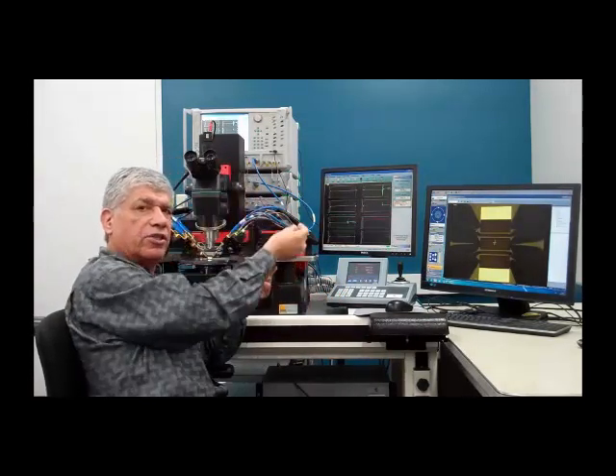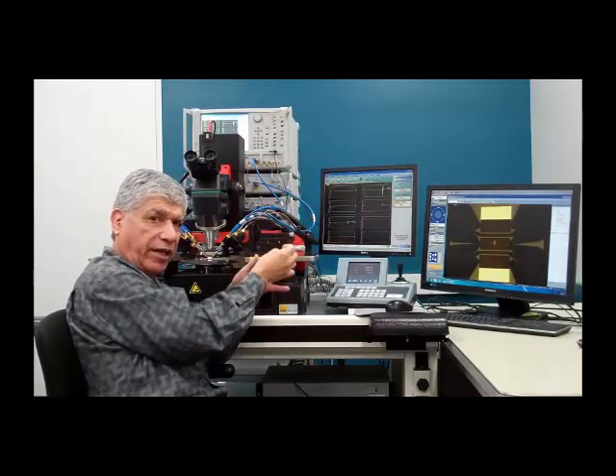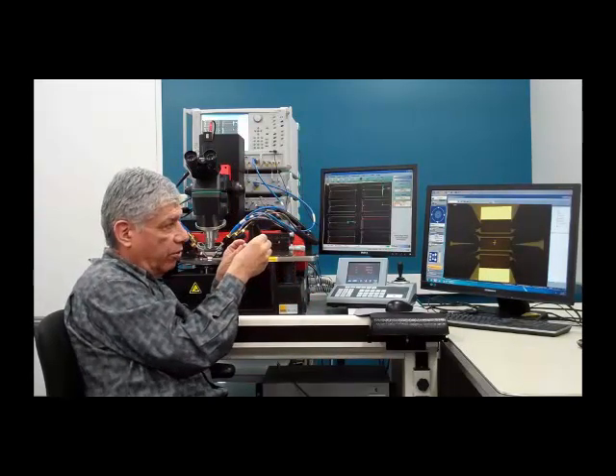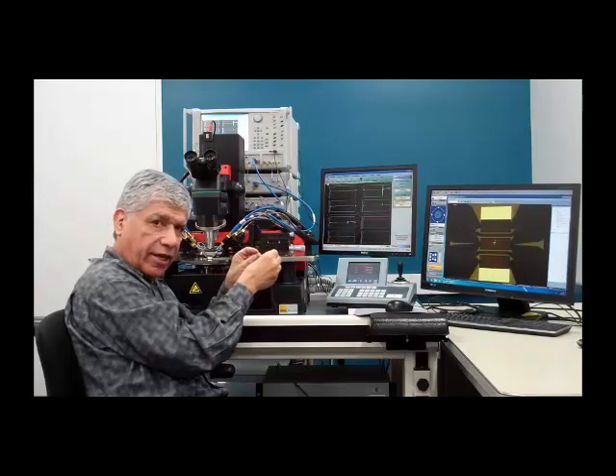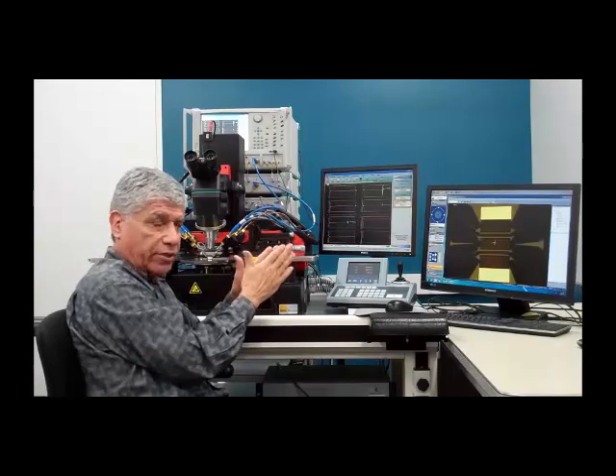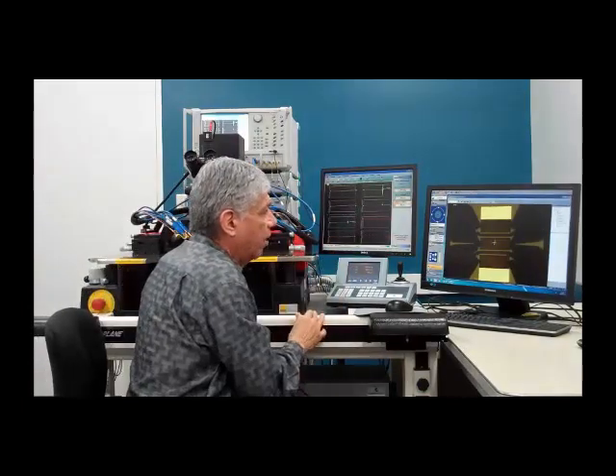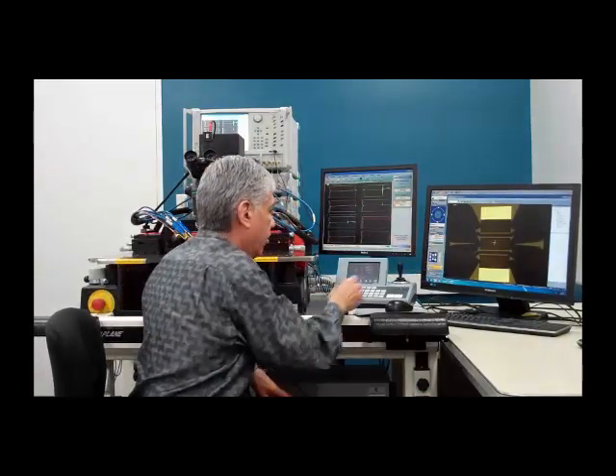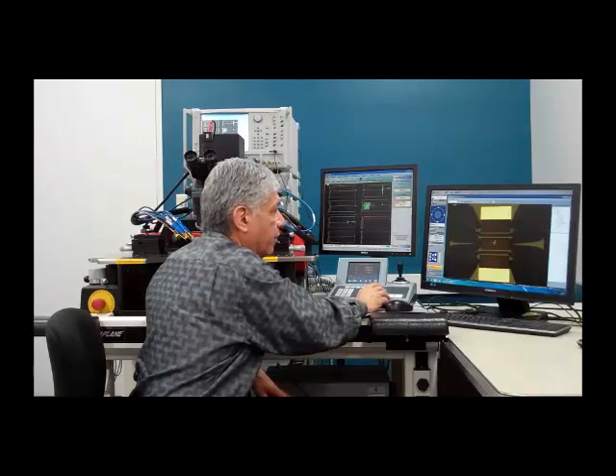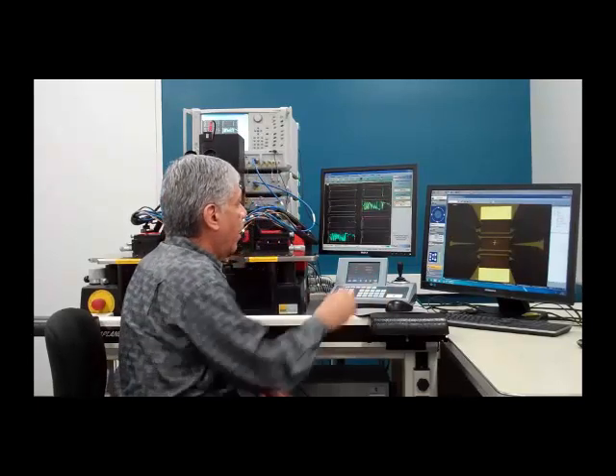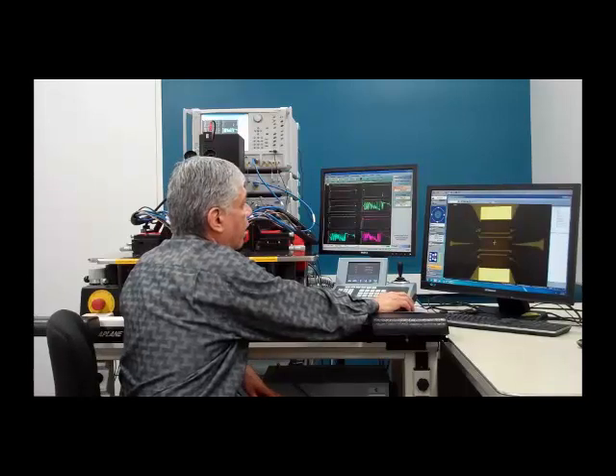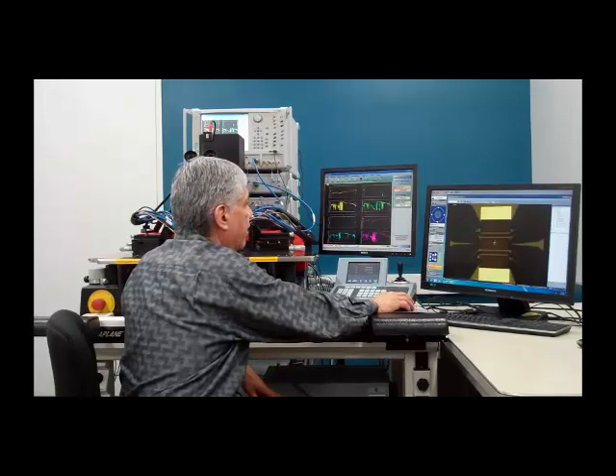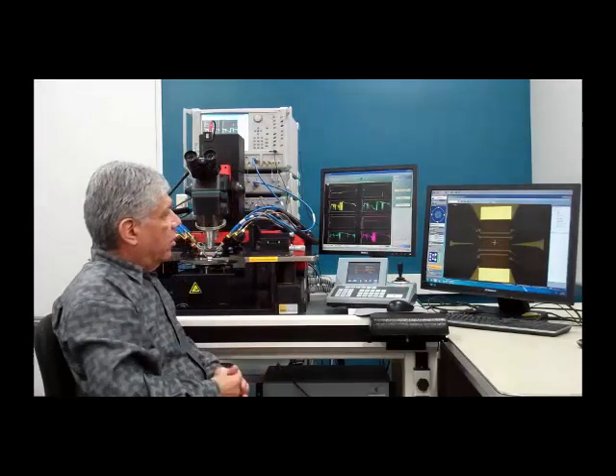So this part is fairly critical, and again, it goes back to the initial calibrations when you were using that alignment tool in order to correctly identify the skating amount so that you get the right amount of separation between the two ports. So now we're positioned properly on our line, and we touch down on our line, and now we can do our port 2, 3 through connection.